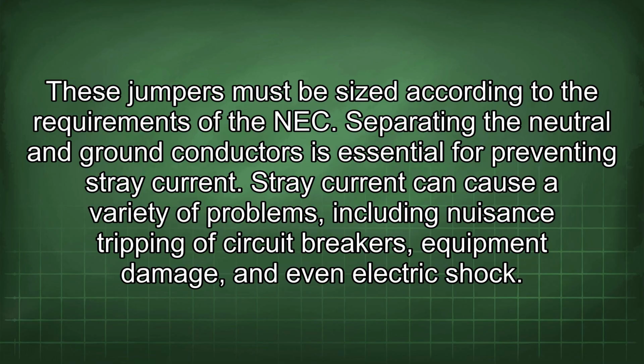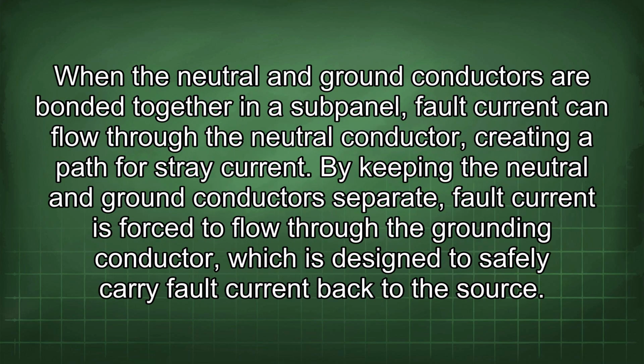Separating the neutral and ground conductors is essential for preventing stray current. Stray current can cause a variety of problems, including nuisance tripping of circuit breakers, equipment damage, and even electric shock. When the neutral and ground conductors are bonded together in a subpanel, fault current can flow through the neutral conductor, creating a path for stray current. By keeping the neutral and ground conductors separate, fault current is forced to flow through the grounding conductor, which is designed to safely carry fault current back to the source.